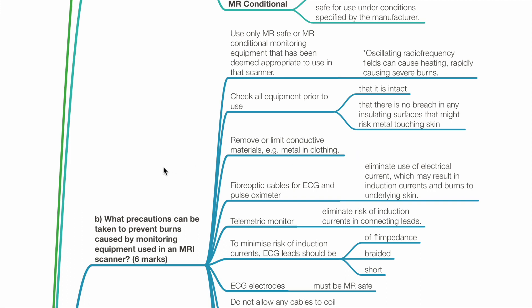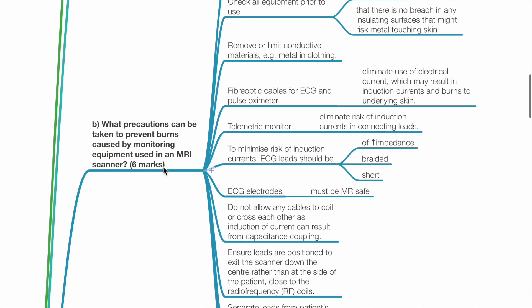Use fibre optic cables for ECG and pulse oximeter. This eliminates use of electrical current, which may result in induction currents and burn the underlying skin. Telemetric monitoring eliminates the risk of induction currents in connecting leads.